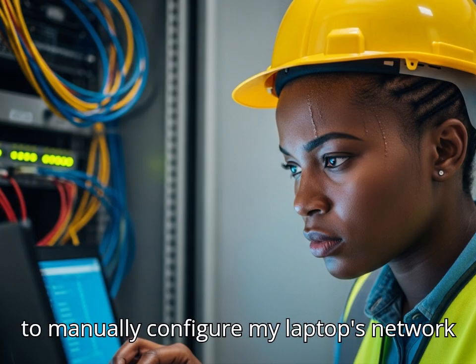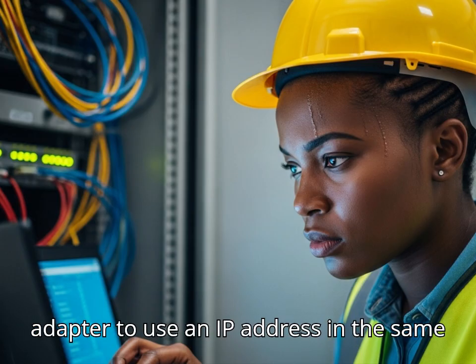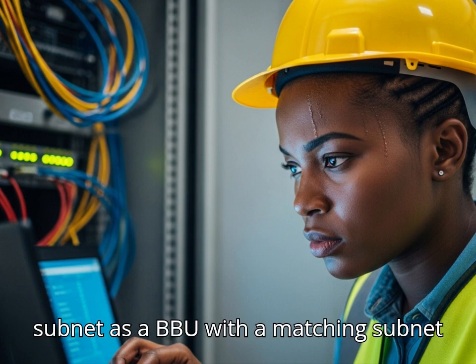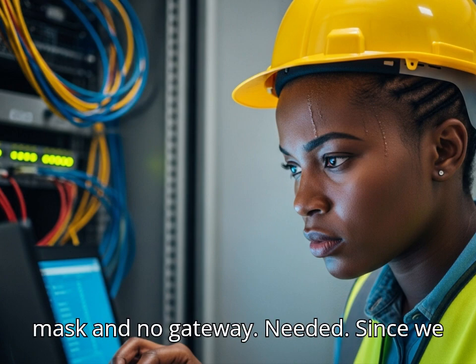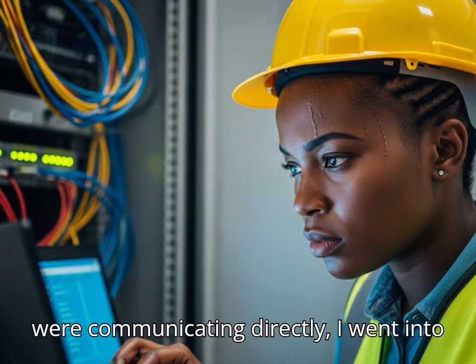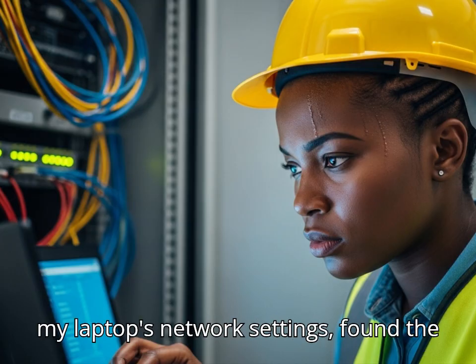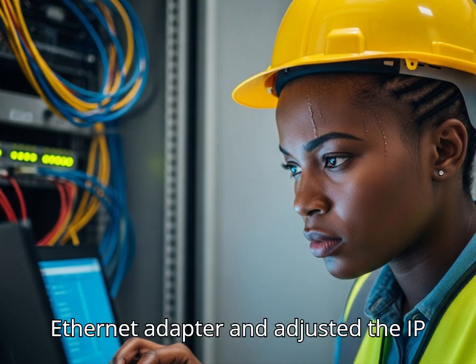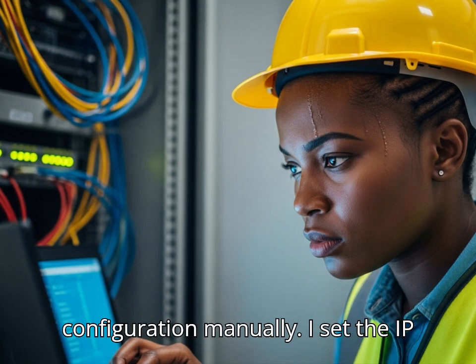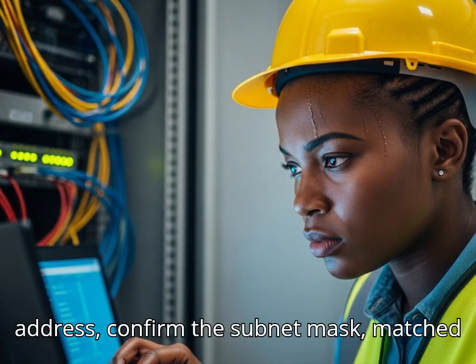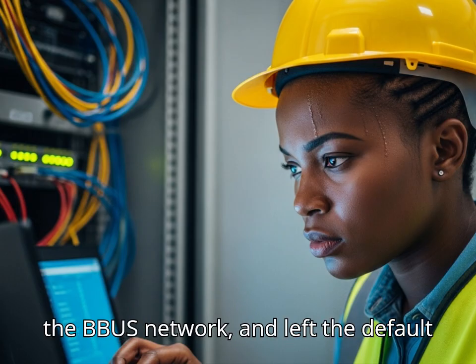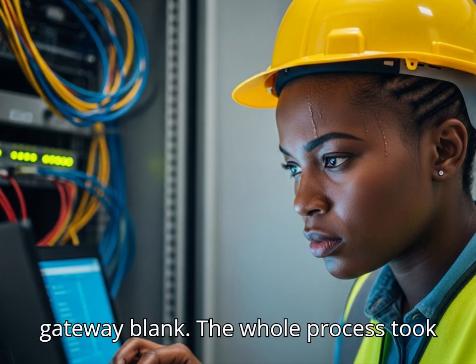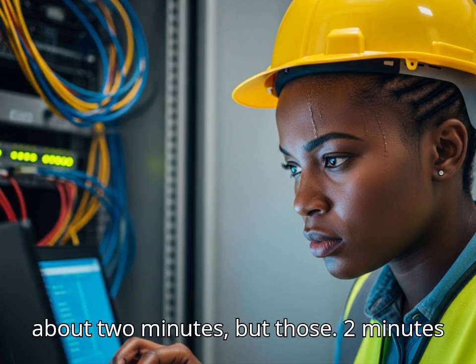This meant I had to manually configure my laptop's network adapter to use an IP address in the same subnet as the BBU, with a matching subnet mask and no gateway needed since we were communicating directly. I went into my laptop's network settings, found the Ethernet adapter, and adjusted the IP configuration manually. I set the IP address, confirmed the subnet mask matched the BBU's network, and left the default gateway blank. The whole process took about 2 minutes.